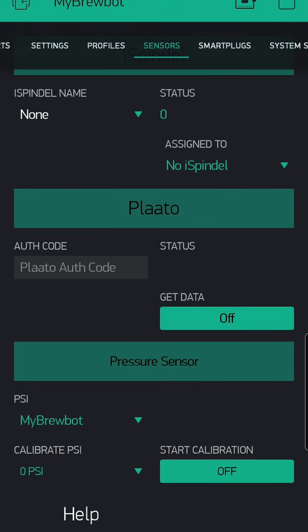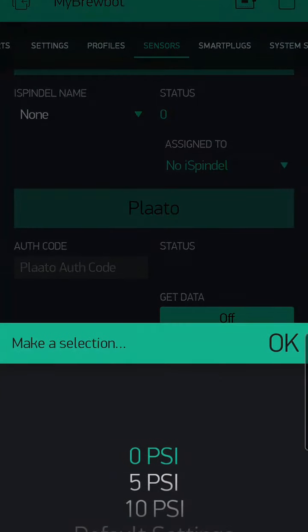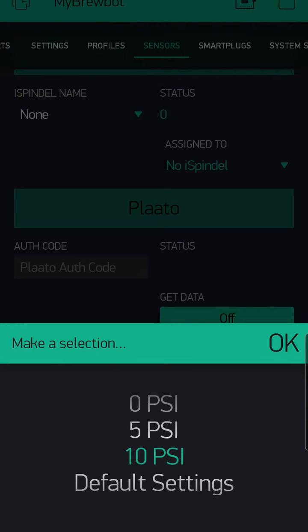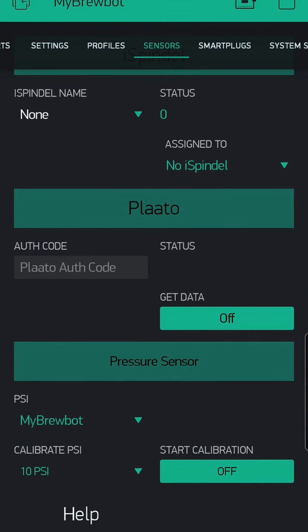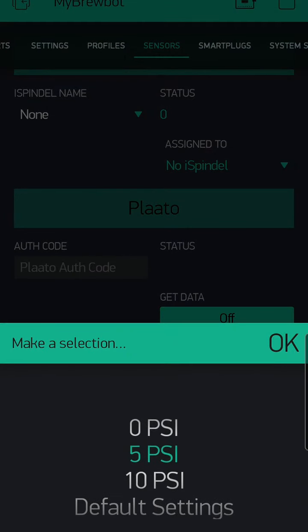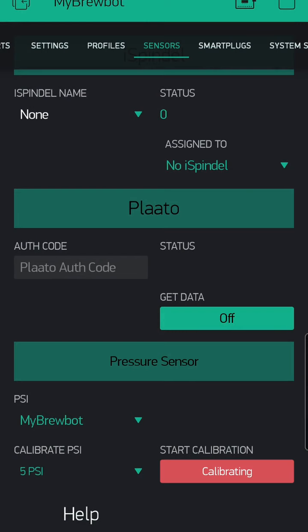To calibrate the pressure sensor, attach it to a pressure vessel charged to 10 psi. Select 10 psi from the Calibrate PSI drop-down. Switch the Start Calibration button to On. Wait. Once calibration for 10 psi has finished, and the UI has returned to normal, reduce the pressure in your vessel to 5 psi and repeat.